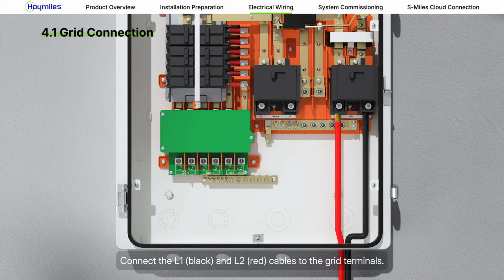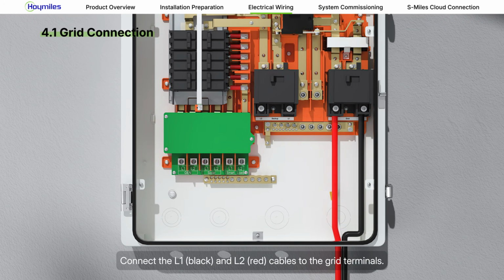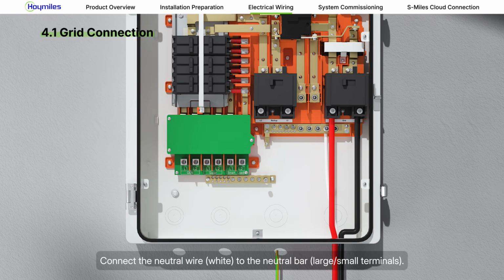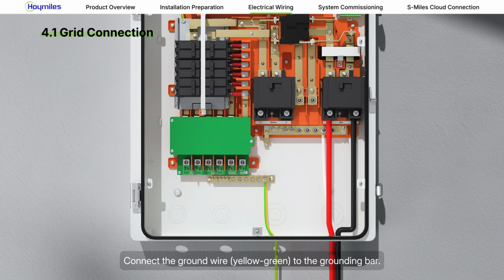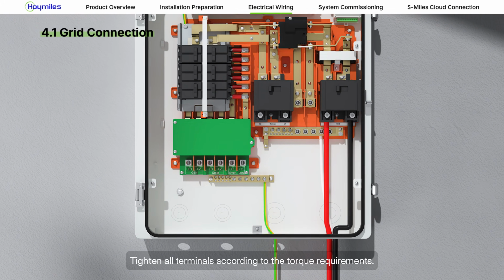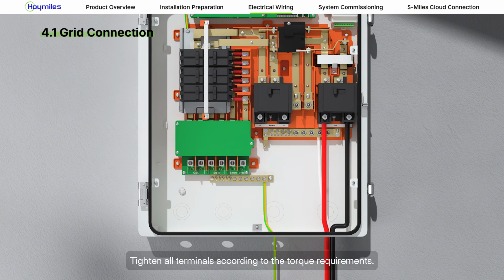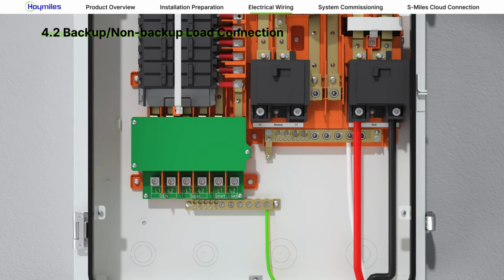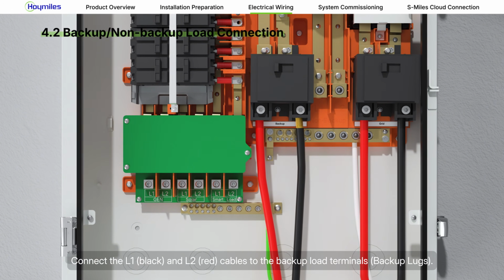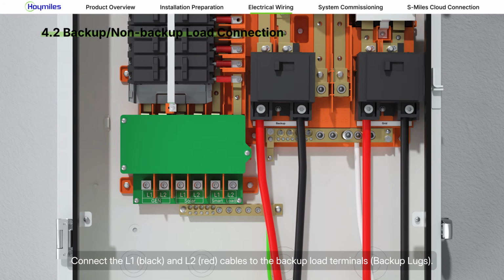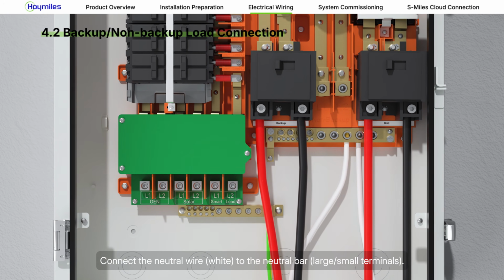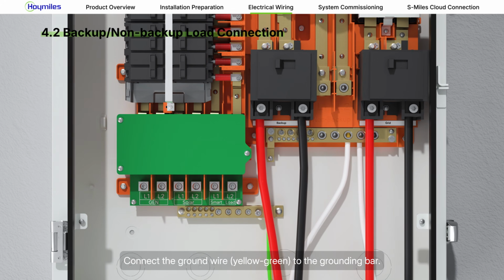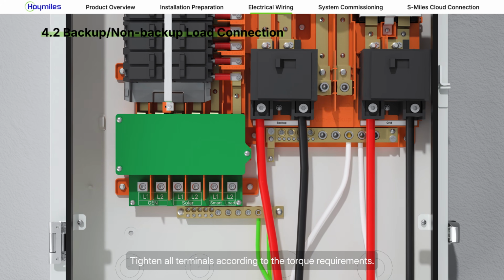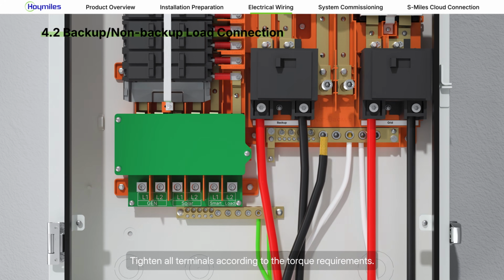Connect the L1 and L2 cables to the grid terminals. Connect the neutral wire to the neutral bar. Connect the ground wire to the grounding bar. Tighten all terminals according to the torque requirements. Connect the L1 and L2 cables to the backup load terminals. Connect the neutral wire to the neutral bar. Connect the ground wire to the grounding bar. Tighten all terminals according to the torque requirements.